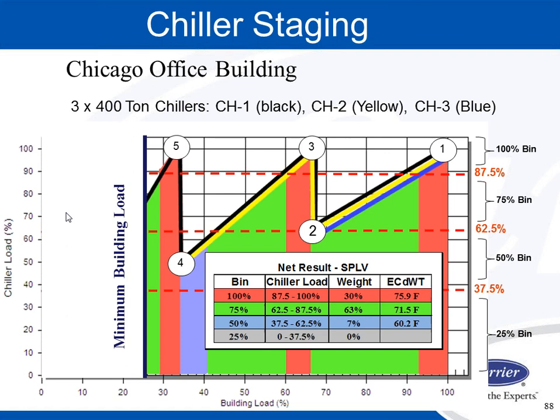Okay, so if we look at the net result, our system part load value, the 100% value happens, we're saying 30% of the time. But it doesn't happen at 85-degree entering condenser water temperature. It happens with an average condenser water temperature of 75.9. The 75% load point happens 63% of the time with an average entering condenser water temperature of 71.5. And the 50% load point happens only 7% of the time with an average condenser water temperature of 60.2. And the 25% load point never happens.